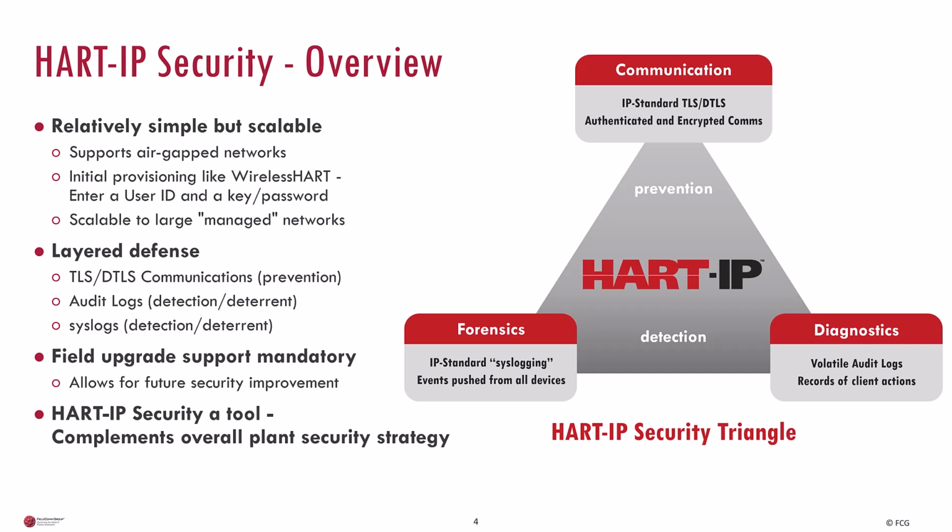Robust security is essential and layered defense was designed. Three major elements were included: communication security based upon TLS and DTLS, and audit logs and syslogs for detection and deterrence purposes. Field upgrades are mandatory. This allows for upgrades to new cipher suites and to address any vulnerabilities that might occur over time. Bear in mind, HART-IP is a tool and is designed to complement your overall plant security strategy.